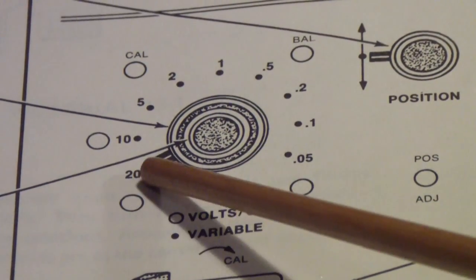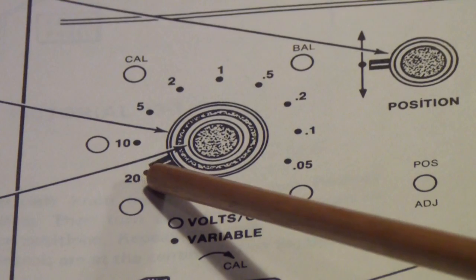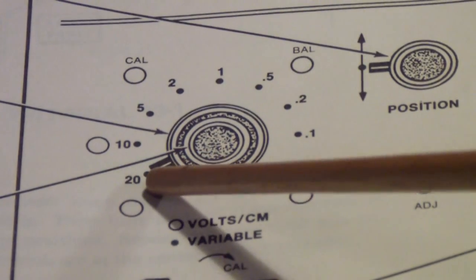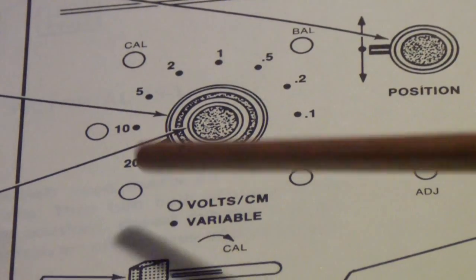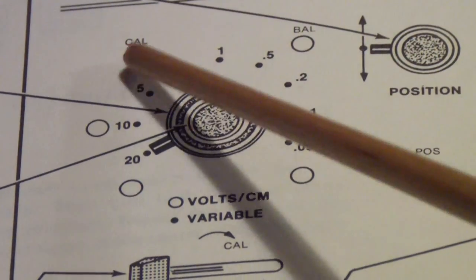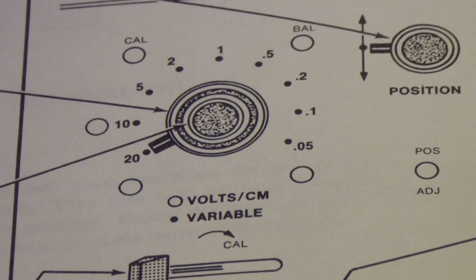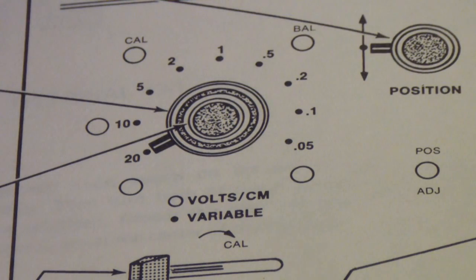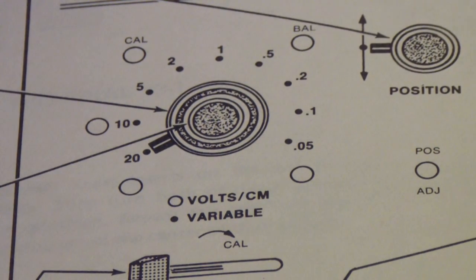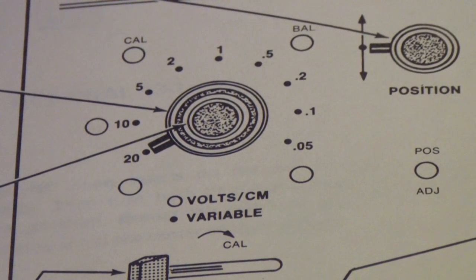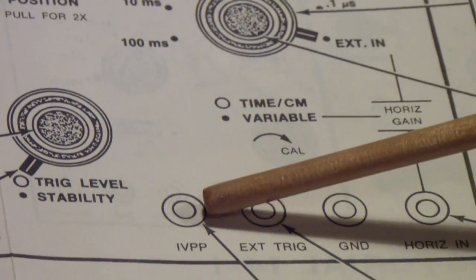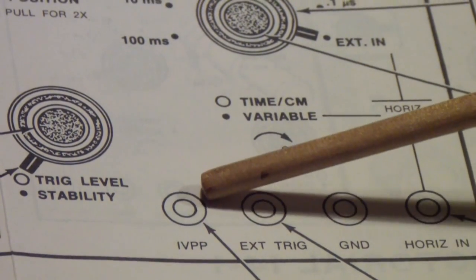You would also calibrate so that the indicated value, when this vernier knob was fully clockwise, was the indicated value. So if it said 10 volts per division, you wanted exactly 10 volts per division. And that was the cal control. And you had to actually go back and forth between these two several times to get a satisfactory result. And that is the purpose, that is setting the cal and the balance, is the purpose of the 1 volt peak-to-peak signal that I referred to in the earlier video.